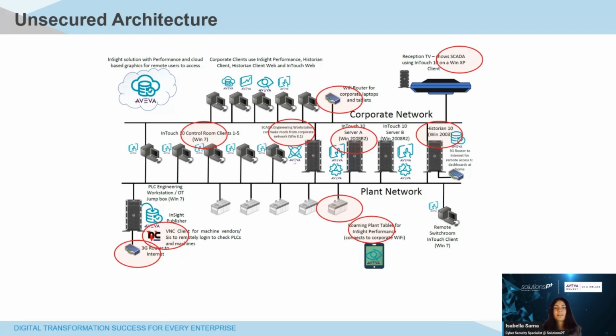There is a lack of segmentation on the network. The corporate and the plant network are not segmented. This means that an attacker who gains access to one of the networks may be able to easily move across to gain access to the other network. You could use a DMZ here, letting the traffic up into the corporate network, but also communicating to the OT network.